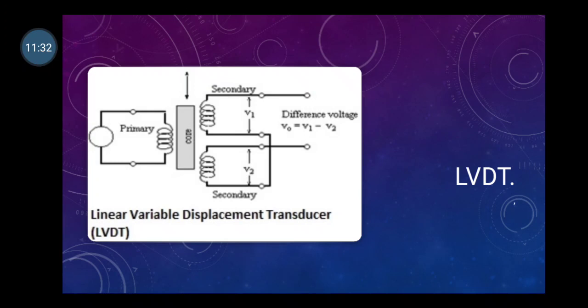This figure shows a linear variable differential transformer. It is a passive transformer. It operates on an inductive principle. It uses to convert the linear motion into the voltage, which is an electrical signal. This primary transducer feeds the signal to secondary transducer, which convert electrical signal to pressure by calibrated scale to read pressure. LVDT's action can be shown in the figure.